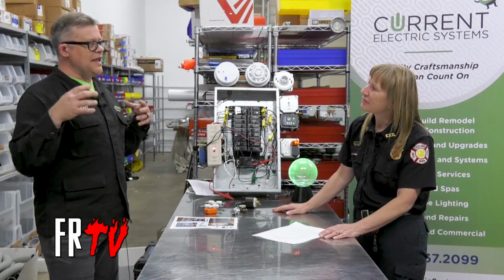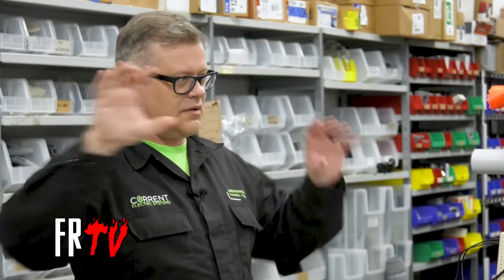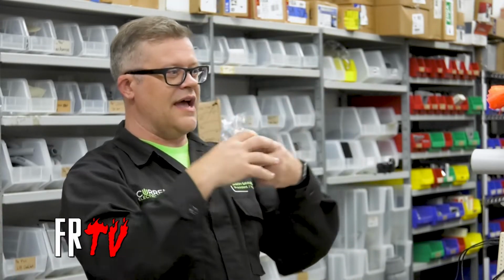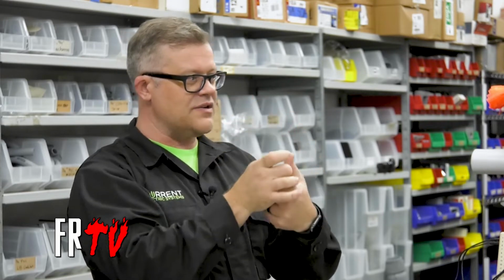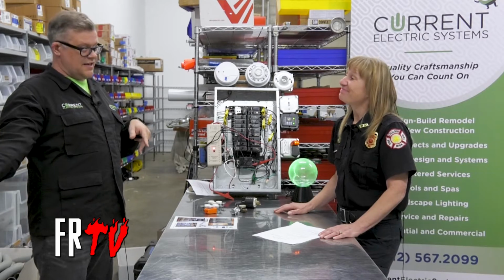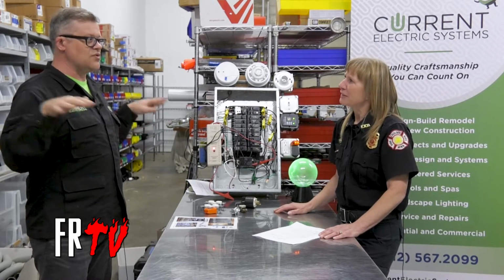Recently we had a client here in Plymouth who had a hot tub installed, and we were there to add a circuit and add in-floor heat in this porch they were redoing. When we climbed up in the attic, we noticed it was just wires, no conduit, not actual cable, not secured, coming right into the panel with no connector, so we had sharp metal and wires right there. This is a 240 volt, 60 amp feeder going to a hot tub, and there's no GFCI.